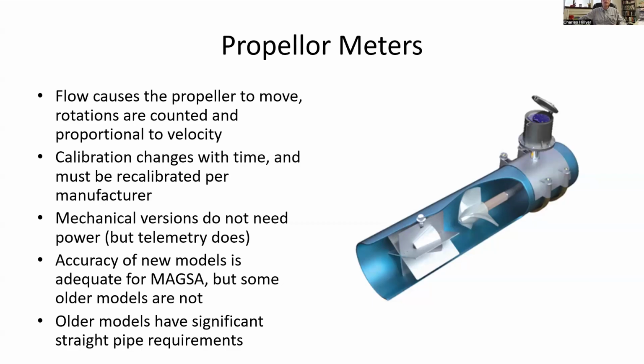But that maintenance is very, very important if you want to reduce the changes in calibration. Some of the old propeller meters were entirely mechanical, which is quite nice because they don't require any power, so you don't have to go out and change batteries. But if you want to know what the flow rate is, you actually have to go out to the meter and look at it, which is kind of inconvenient.